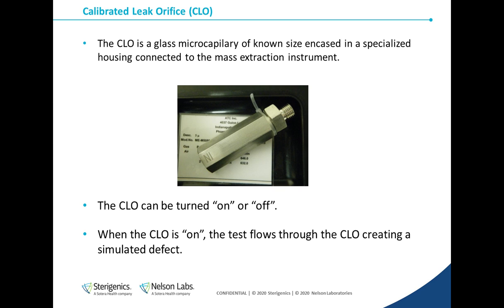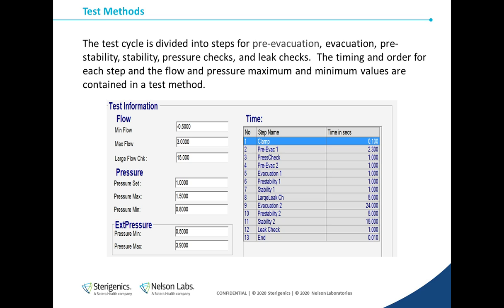Having a built-in defect is really handy because it eliminates the need to create defects in the actual test samples. Intentional defects from laser drilled holes, microtubes, or sealing wires in the closure have some inherent problems. So this is a feature that we really love about this instrument. The CLO is our positive control for the test. A CLO value is generated by running the master with the CLO switch turned on. And this is done with every test set, so we have a flow value for a defect of known size in the specific test system.